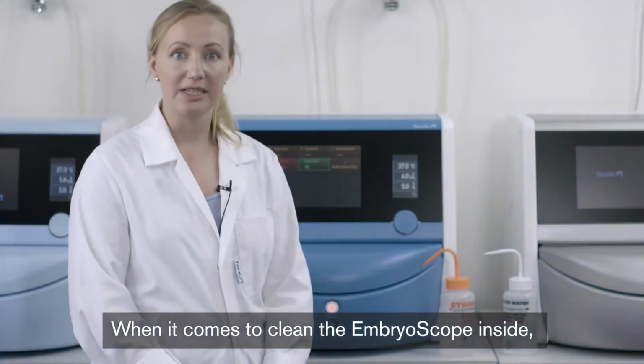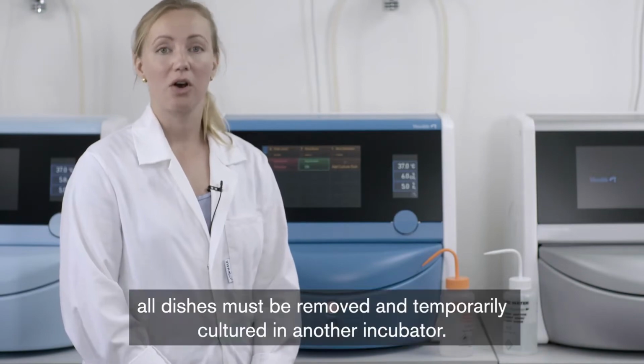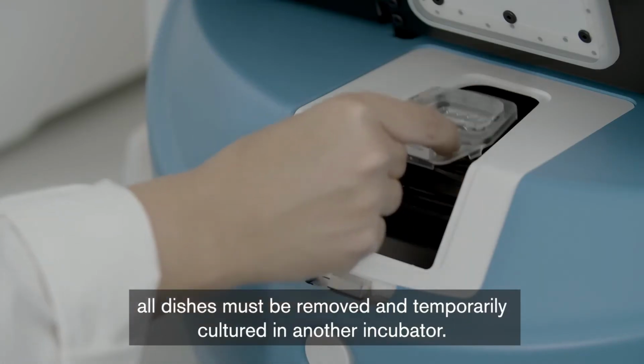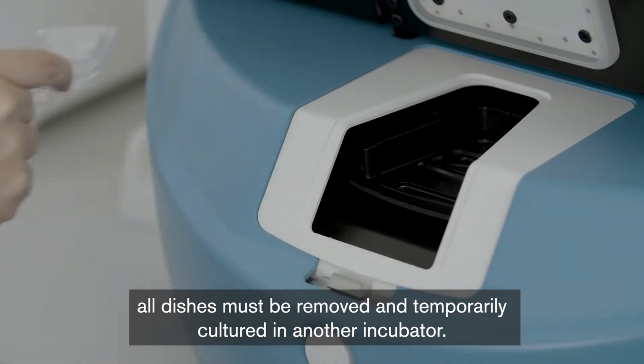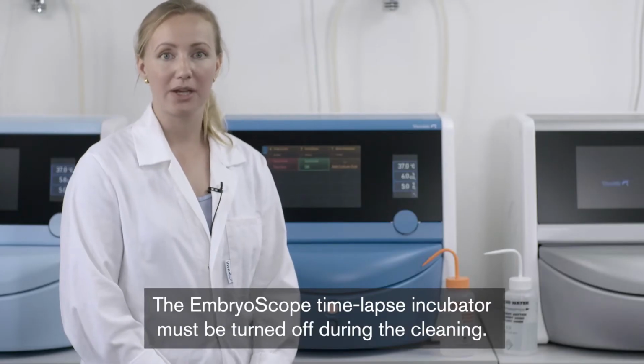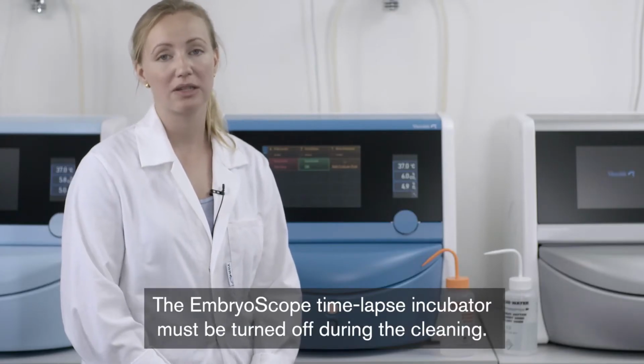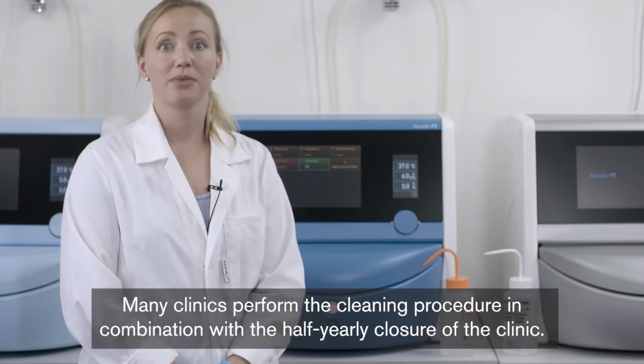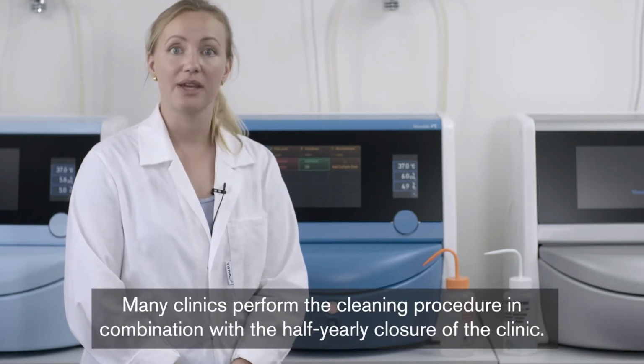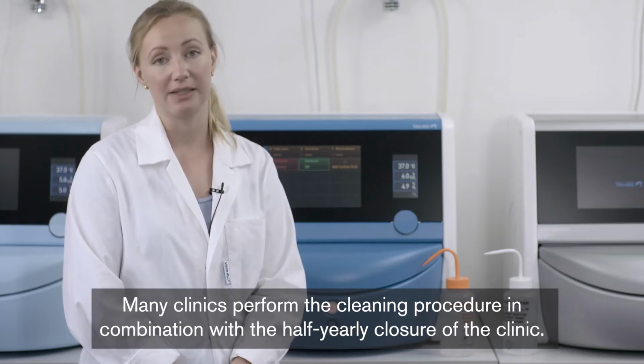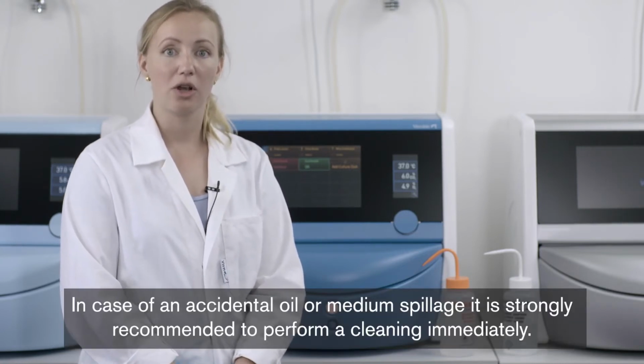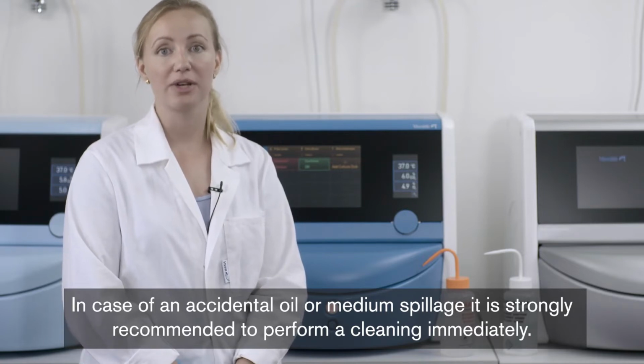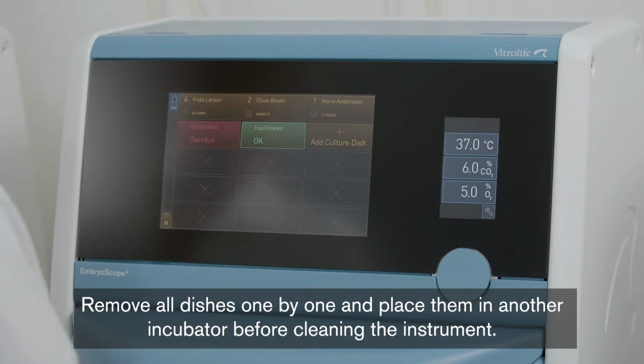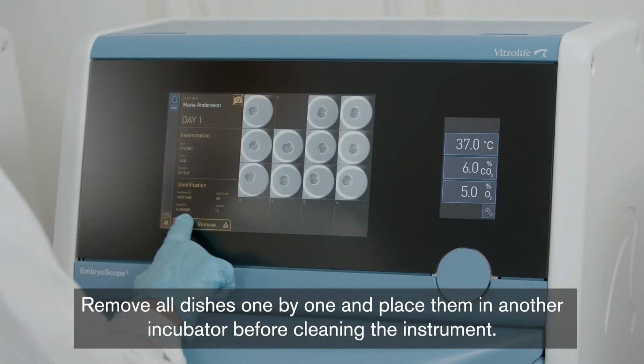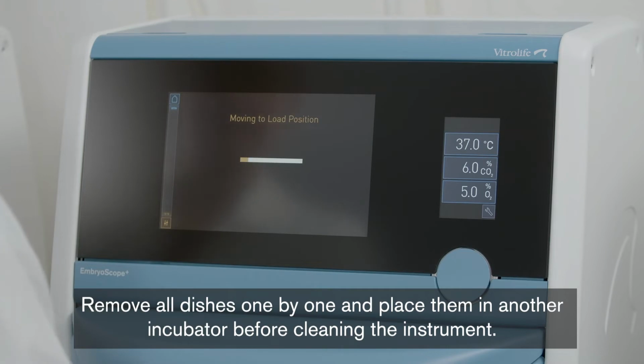When it comes to cleaning the EmbryoScope inside, all dishes must be removed and temporarily cultured in another incubator. The EmbryoScope Time-Lapse incubator must be turned off during the cleaning. Many clinics perform the cleaning procedure in combination with the half-yearly closure of the clinic. In case of an accidental oil or medium spillage, it is strongly recommended to perform a cleaning immediately. Remove all dishes one by one and place them in another incubator before cleaning the instrument.